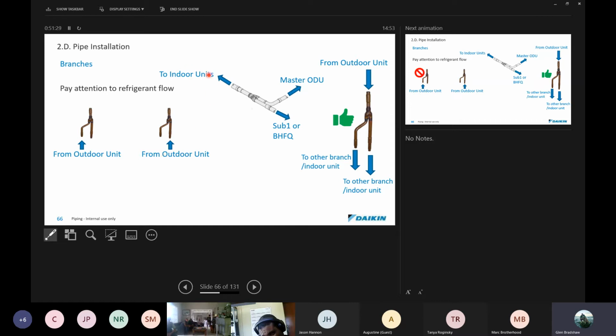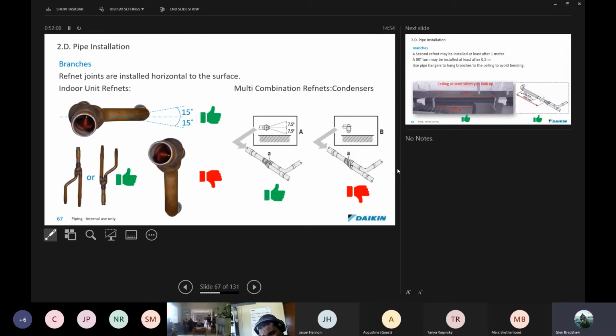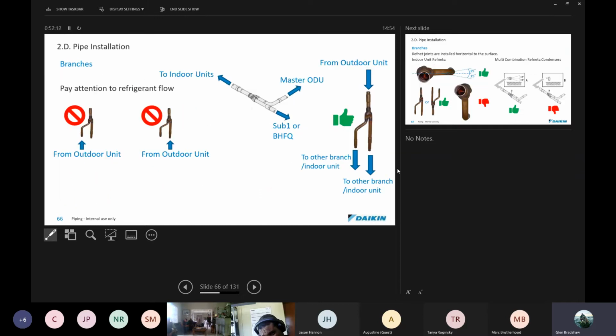All right, so this goes over here. This is a diagram showing the indoor units. So basically that's not the flow. This is at the condenser, for instance. That means the refrigerant in this joint is coming back in this direction over here, and going to the master outdoor unit and then onto the sub unit. So here again, like I said, flow must always be in from this side over here, and then through the two. So those are not allowed. And this is the preferred one over here.